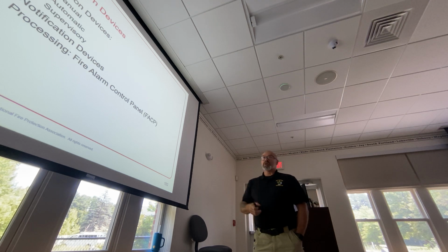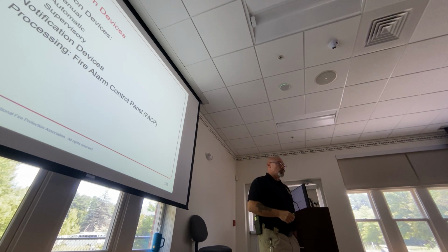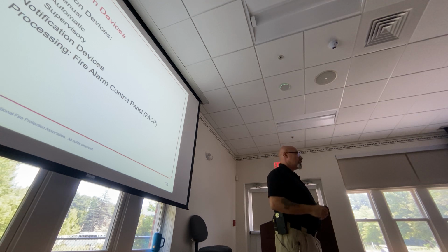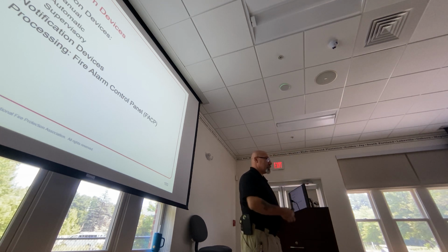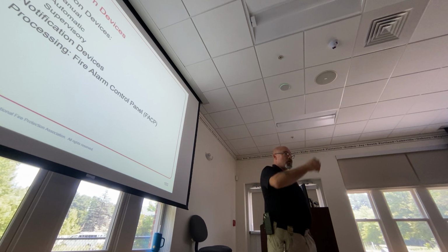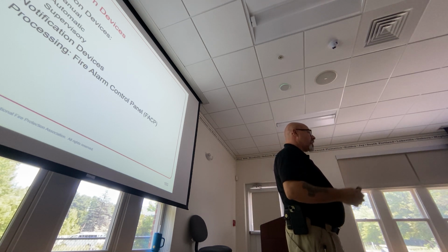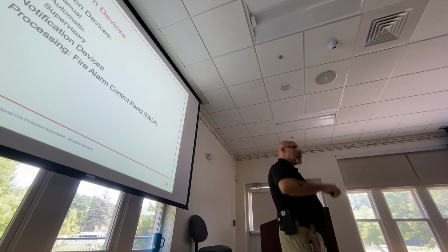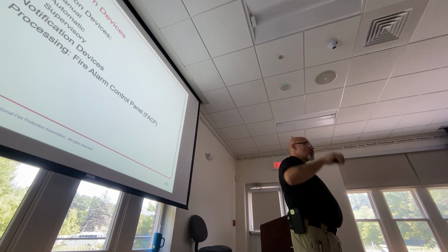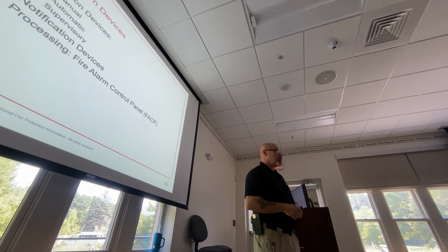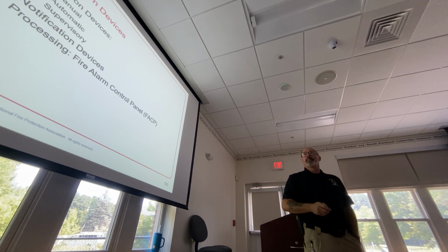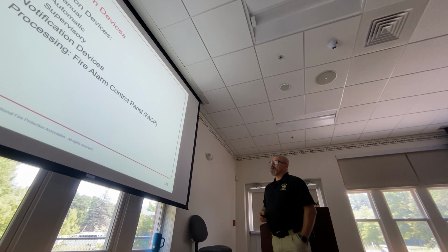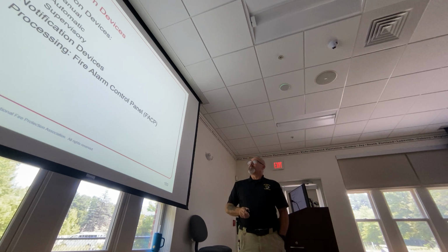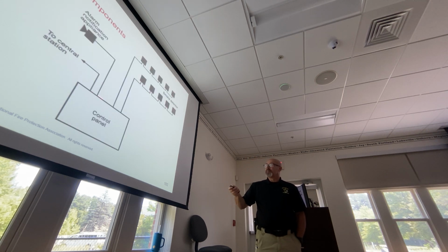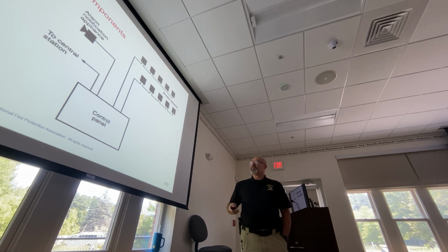Then we have our notification devices, as I pointed out: horns, strobes, it could be a screen. Some large facilities like the Bangor waterfront or the Cross Centers, if a fire alarm goes off, they actually have it on the screen: fire alarm, emergency, exit the building, walk, don't run. And then we have the processing portion of it, which is the fire alarm control panel. This thing right here is the brains. It receives all the signals and sends signals out.